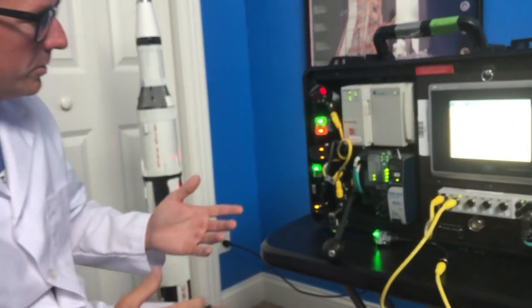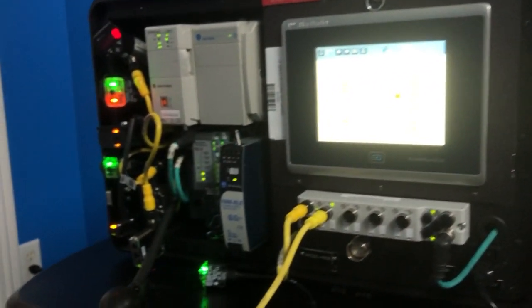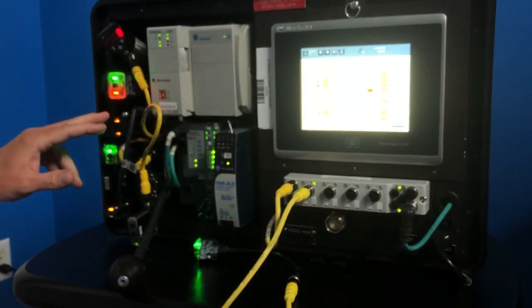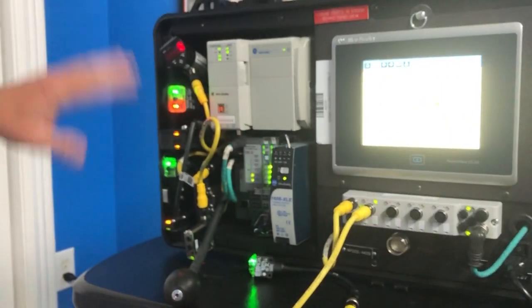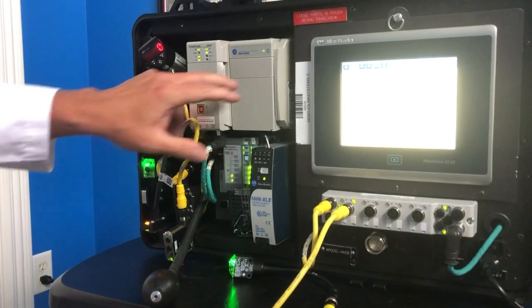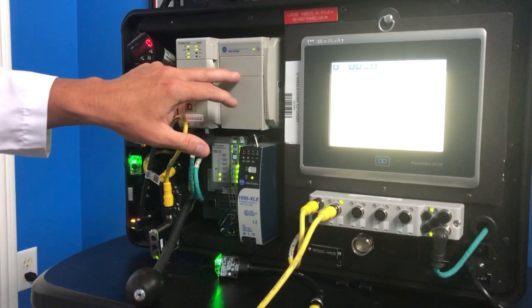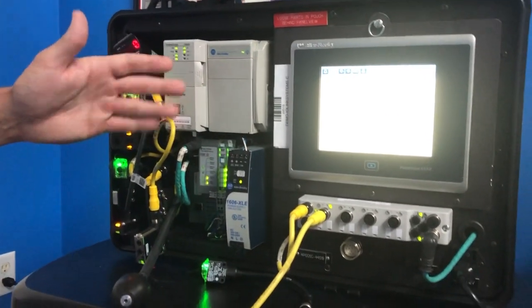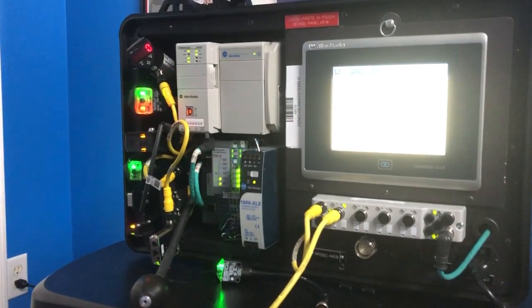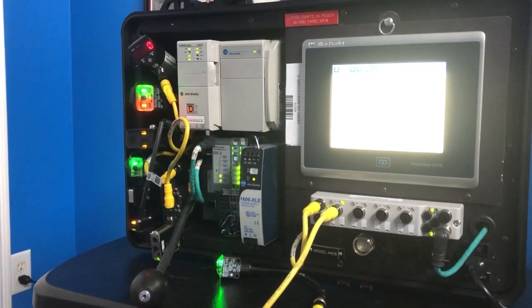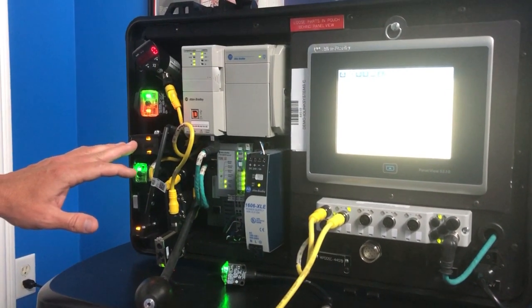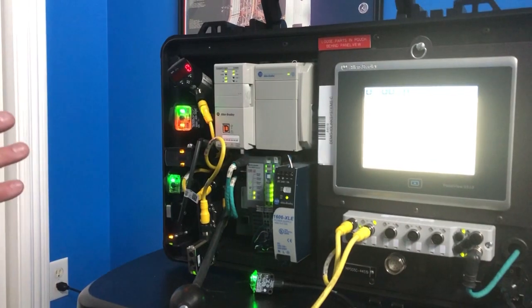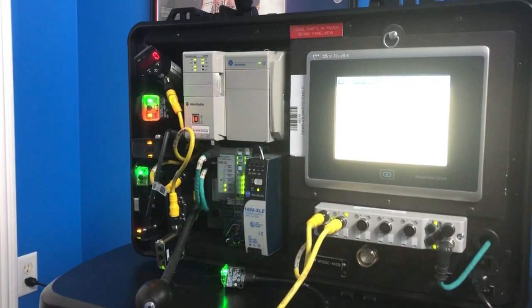Some other key features, too. Let's say I have a sensor set up here that has a certain set point out here. Well, we also have automatic device configuration. So anytime I'm setting these sensors up, the data and the set points is stored inside the processor. So at 2 o'clock in the morning, if I actually have one of these sensors go down, I can unplug it, plug a new one right back up, and I'm back up and running. I never had to change anything about the sensor whatsoever.